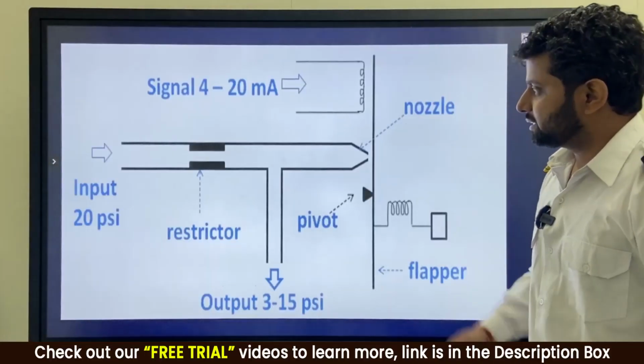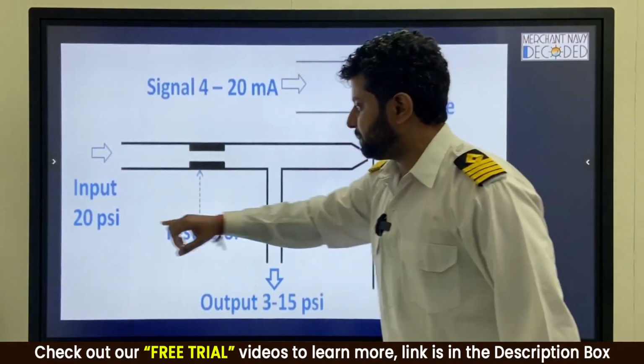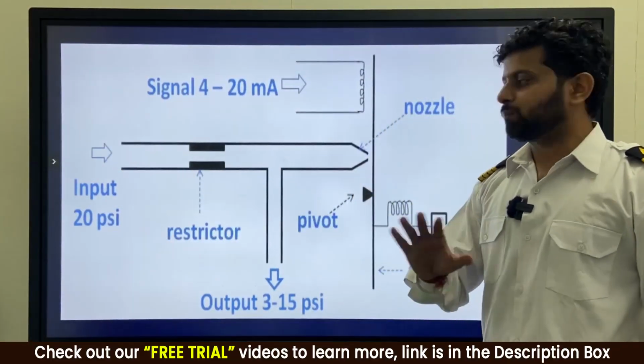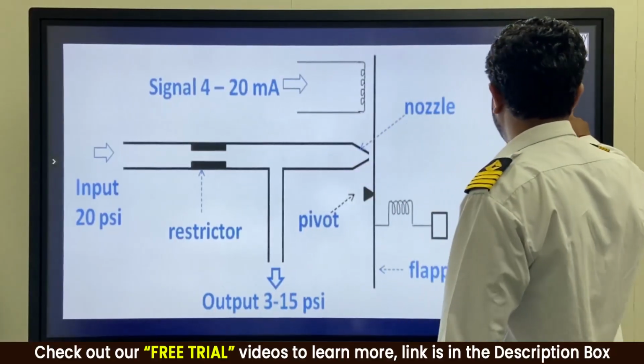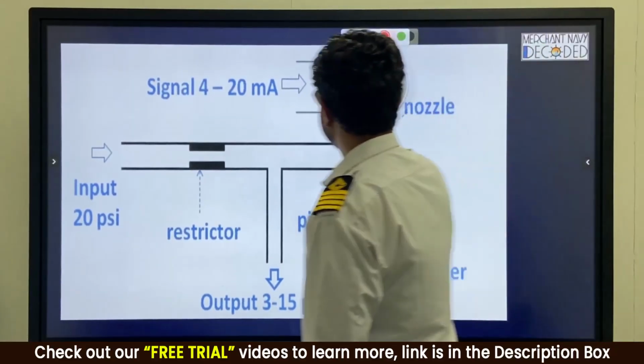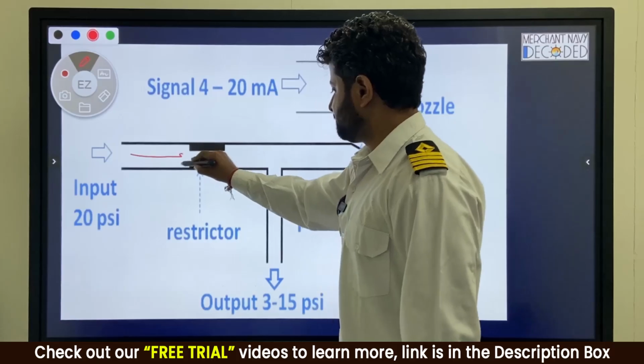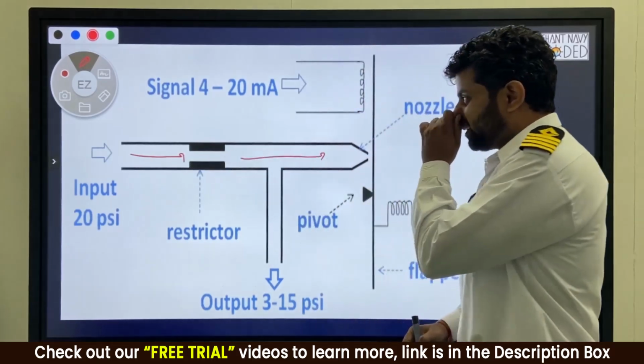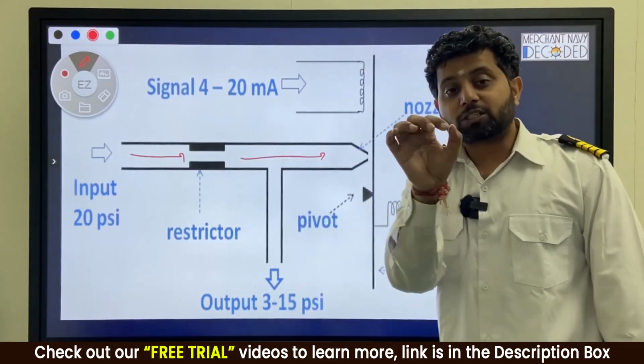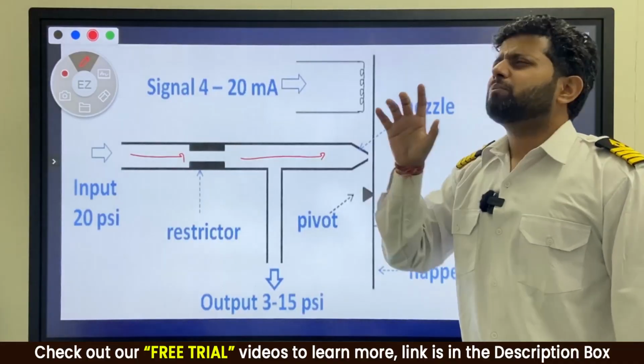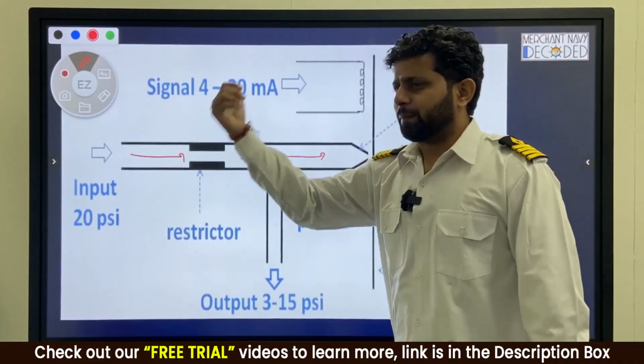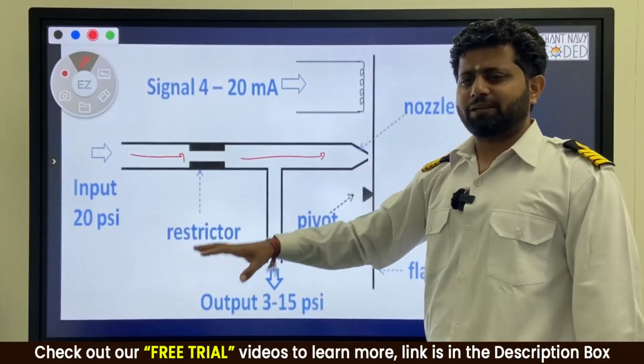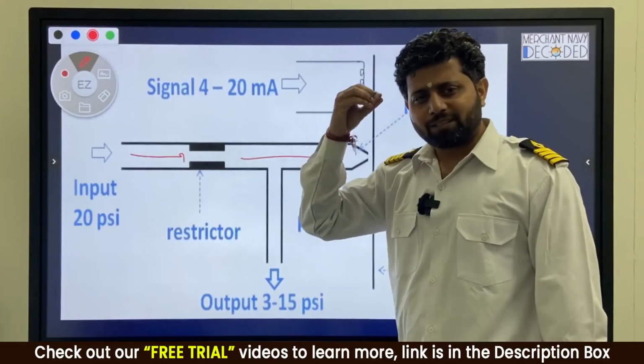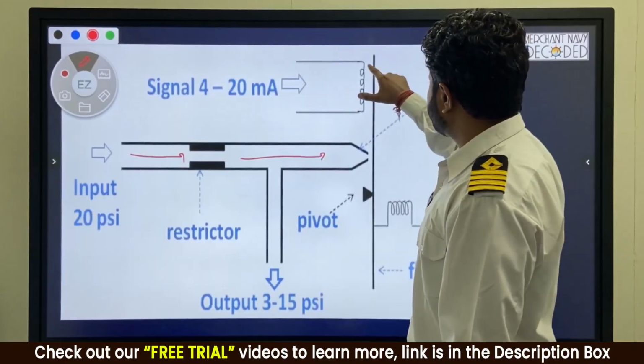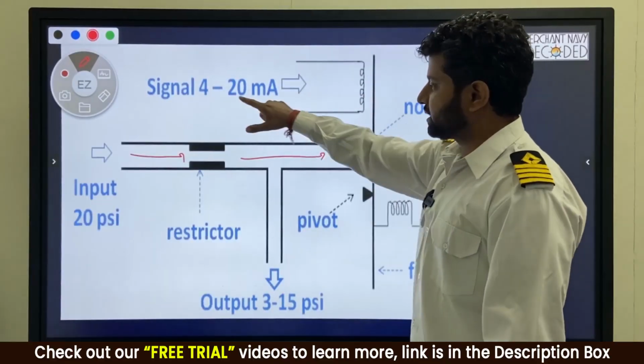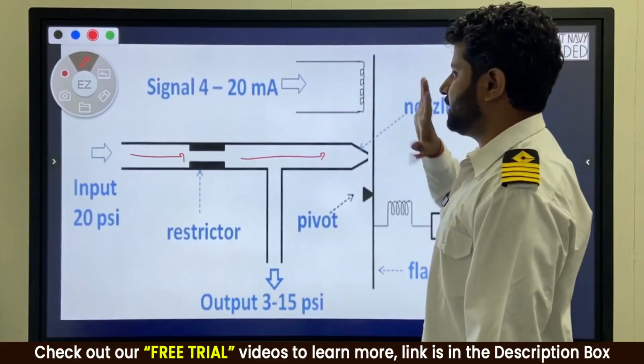Okay, so now see guys. This is the input air which is 20 psi. If you convert 20 psi, it is around 1.4 bar. It comes from over here. There is a restrictor. It comes over here. Now the signal 4 to 20 milliamps is coming from the unbalanced transducer. Maybe this unbalanced transducer is fitted in a capacitive type, resistive type, XYZ type, fitted anywhere. So when this unbalanced transducer is fitted over here, the signal coming from it gives 4 to 20 milliamps current.